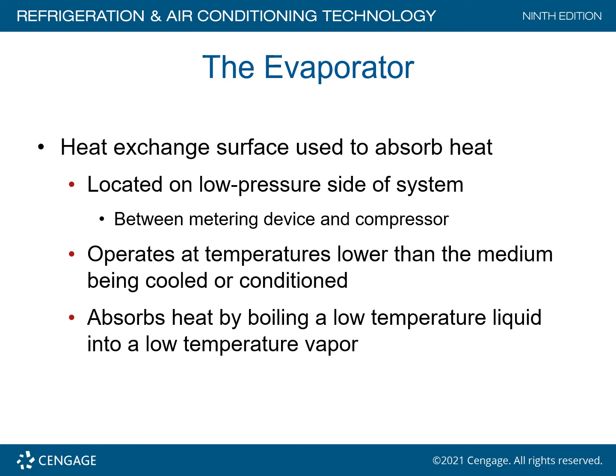Evaporator and refrigerant. The refrigerant typically enters the evaporator as a liquid vapor mix, 75% liquid, 25% vapor. Superheat. This is a term you're going to see a lot. The heating of the vapor above its saturation temperature ensures that no liquid refrigerant enters the compressor. On the gauge manifold sets that you will be using in the lab, we are going to be utilizing, as an example, a Fieldpiece 360 or 460. There are other brands also available. Those digital gauges have clamps which measure superheat and subcooling. We do monitor the superheat.